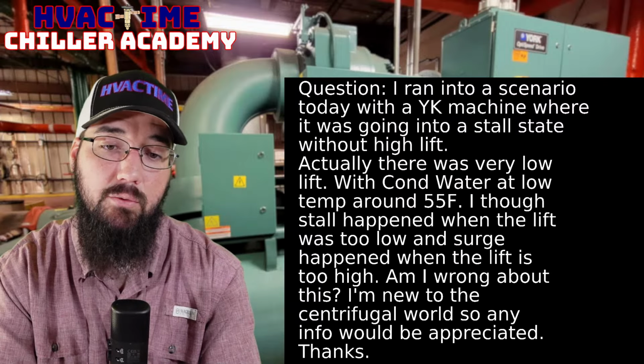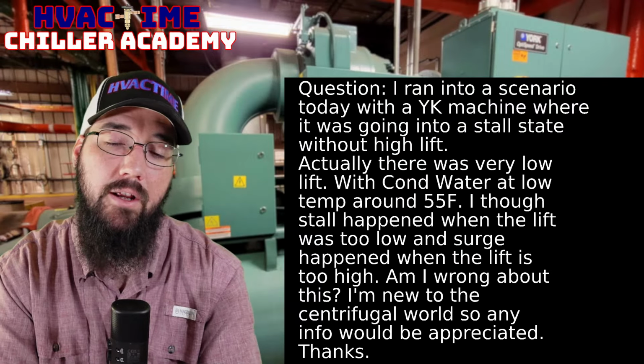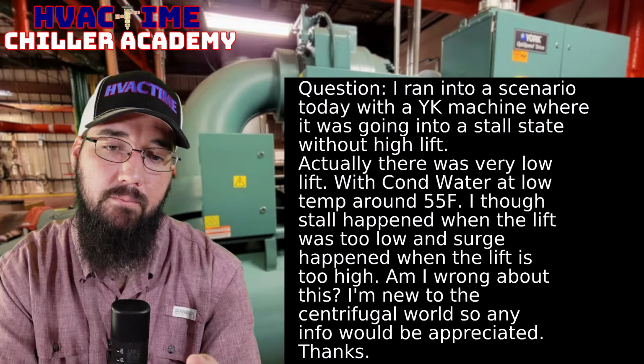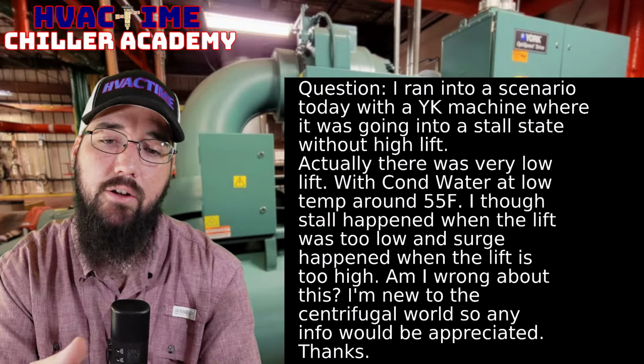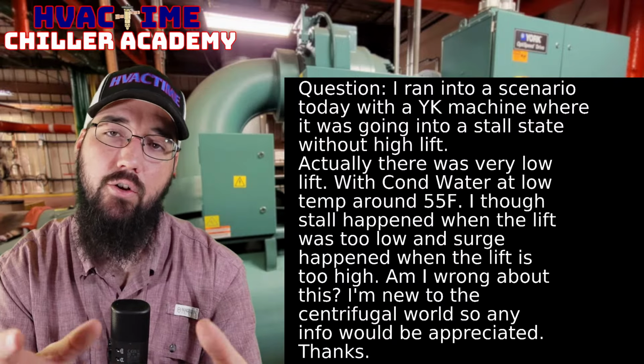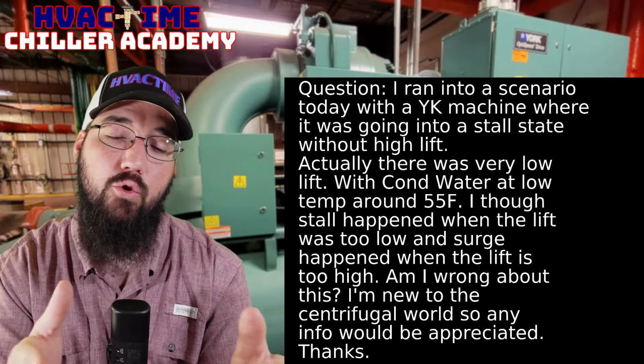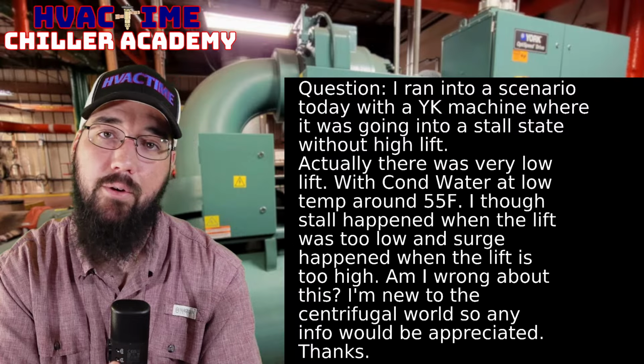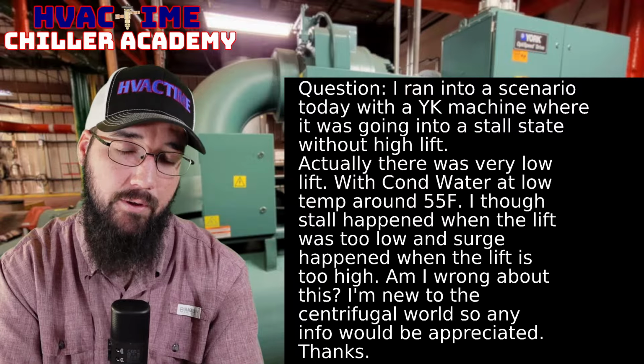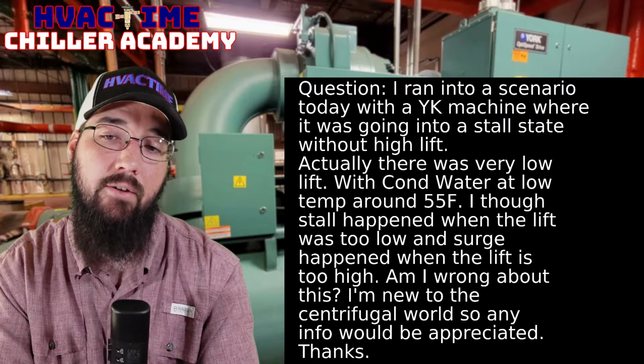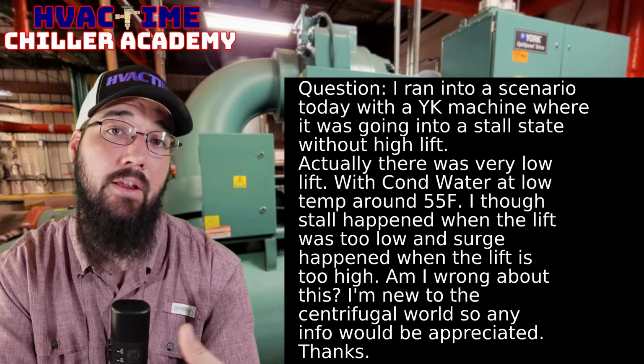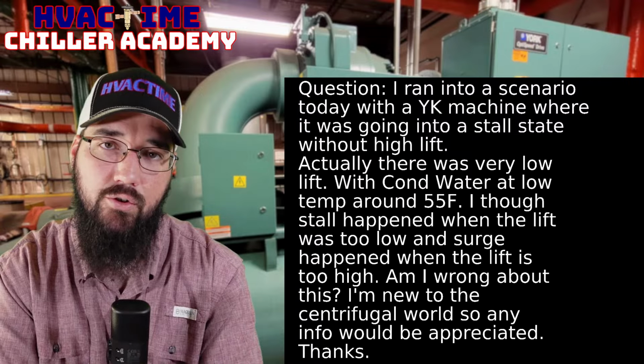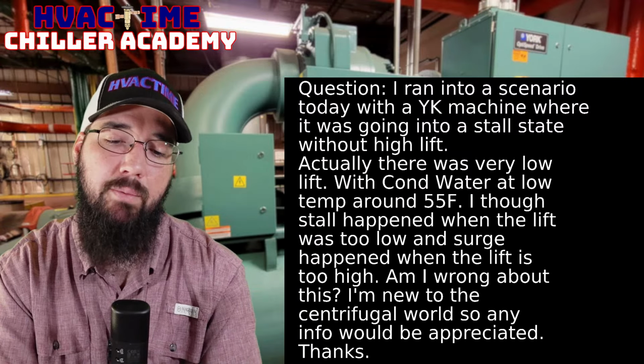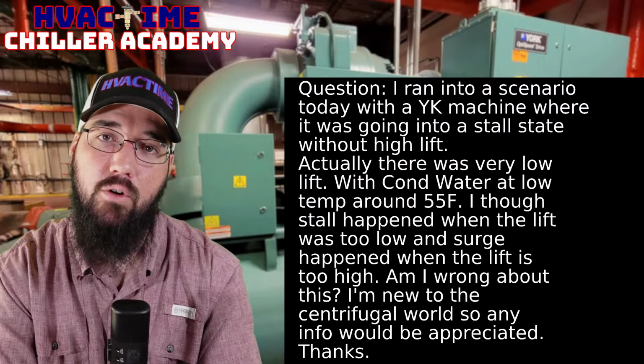And it's possible that if you're not running a minimum lift or ratio, you could be stacking oil in your evaporator because you're not able to return it properly. It may run like that for a period of time just fine, and then it suddenly starts having surging issues. And what I would expect to see then is your approach probably increased.